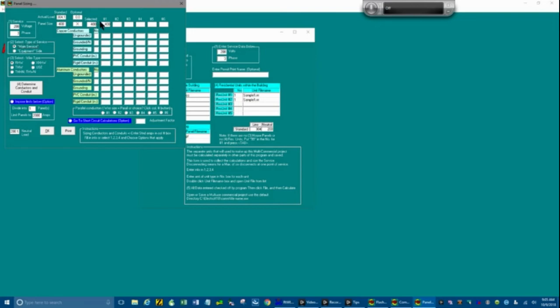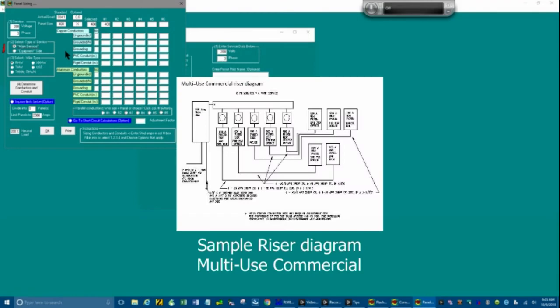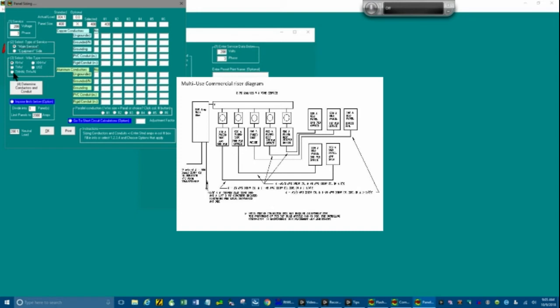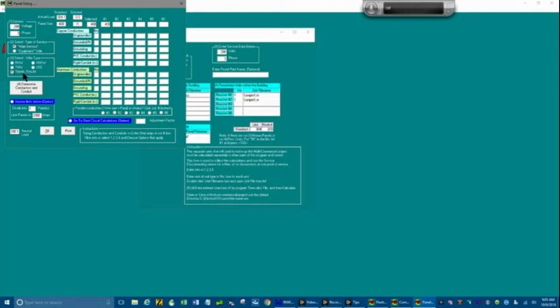And you'll notice that it selected one 400 amp for the main service. So that means your main service disconnect is going to be there. And then you'll have separate units which were calculated in your previous calculations for the panels that will be attached at this one point of service. So we'll choose THHN. And again, your instructions are here. Fill out the instructions.